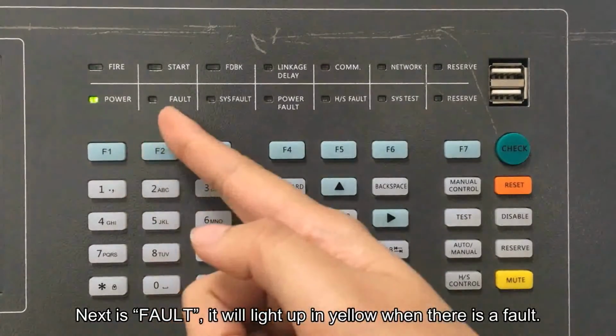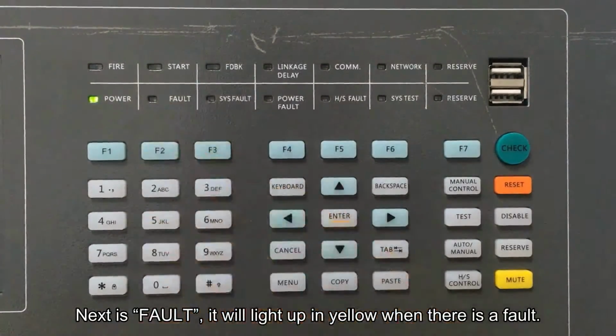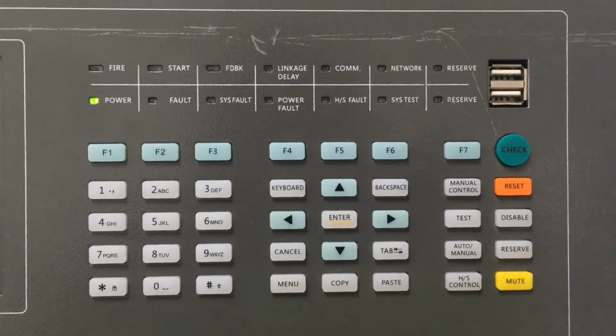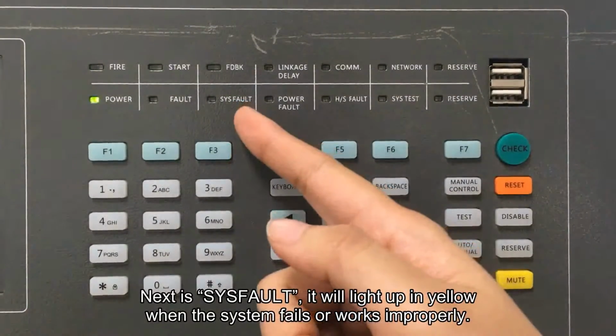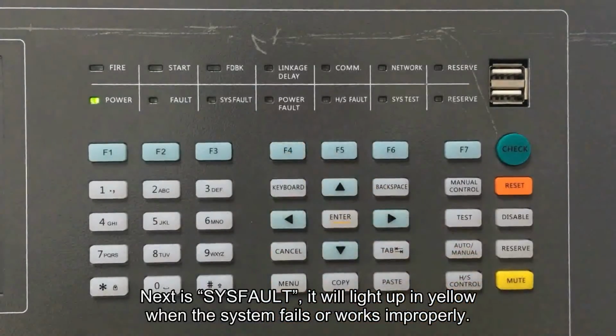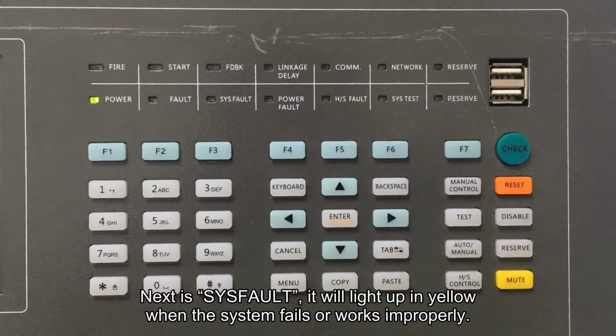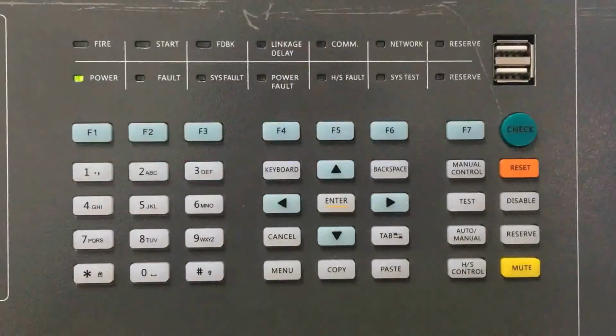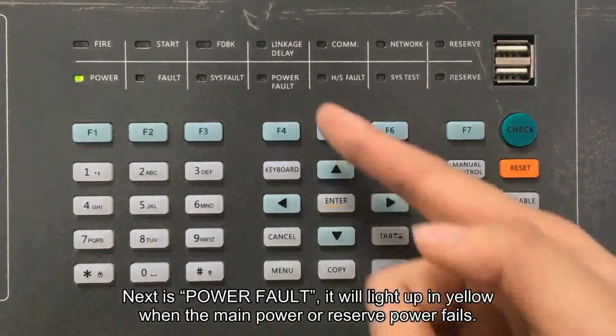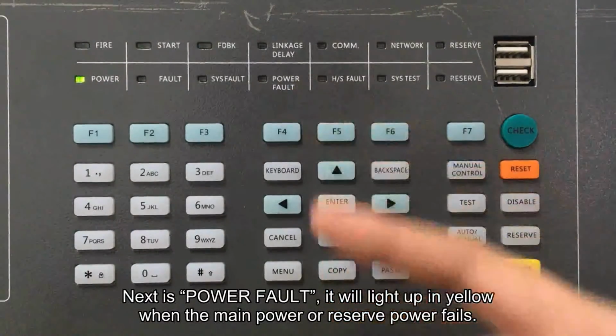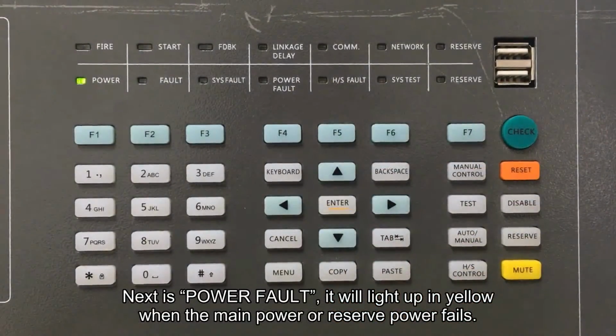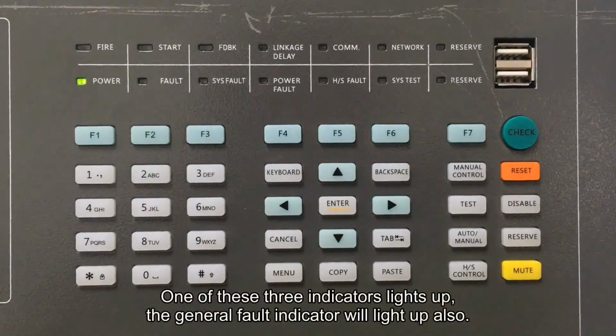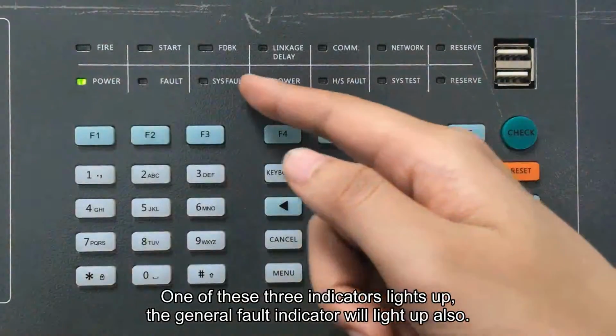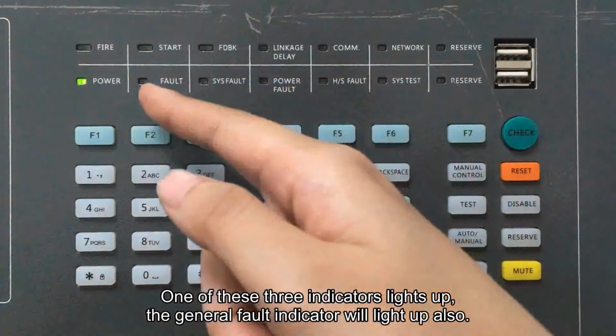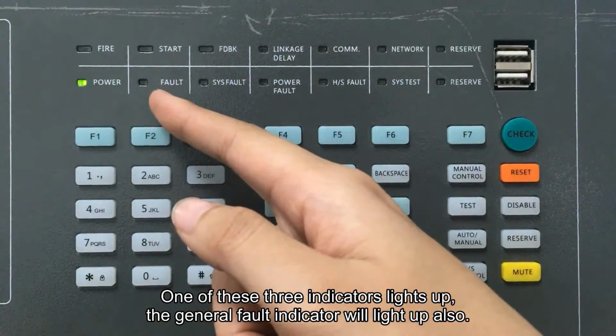Next is fault. It will light up in yellow when there is a fault. Next is sysfault. It will light up in yellow when the system fails or works improperly. Next is power fault. It will light up in yellow when the main power or reserve power fails. If one of these 3 indicators lights up, the general fault indicator will light up also.